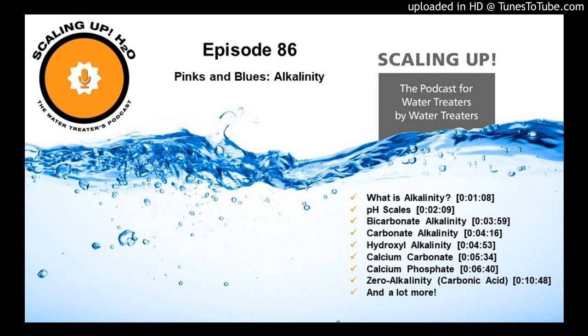One of the insurance policies that we have in a boiler, so we don't create that in a phosphate program, is we have extra free hydroxyls in the boiler water to make sure that we create that hydroxyapatite. And I know that's a really strange word, but just remember this: calcium phosphate, hard and will crack concrete walls. Hydroxyapatite, nice fluffy snow. And we have that nice fluffy snow that goes down to the bottom of the boiler.